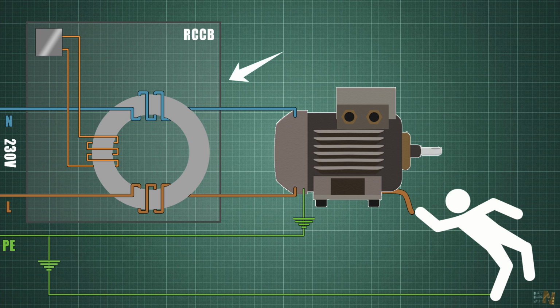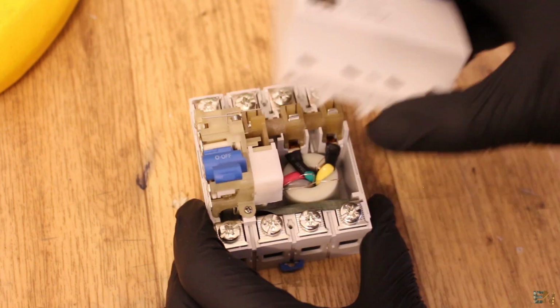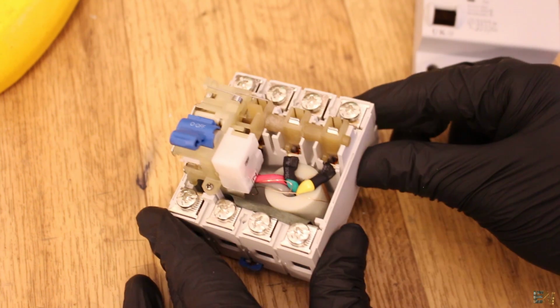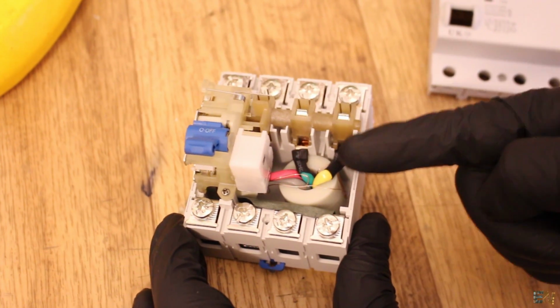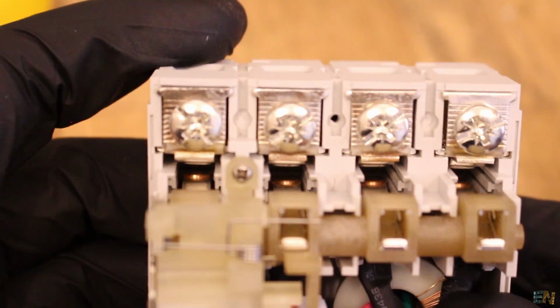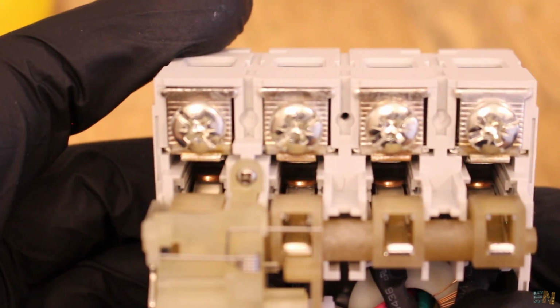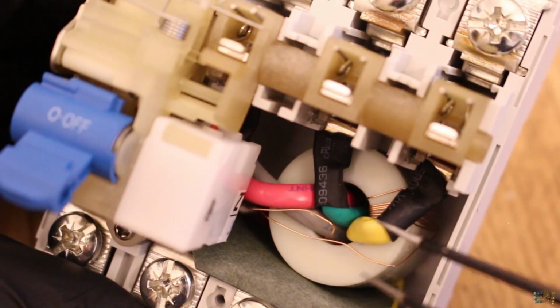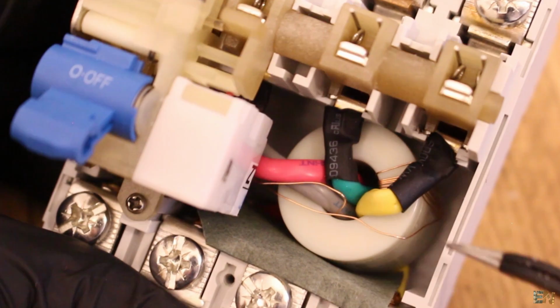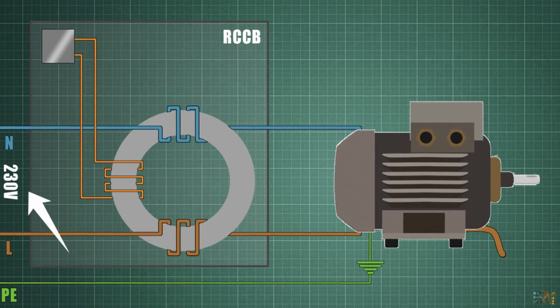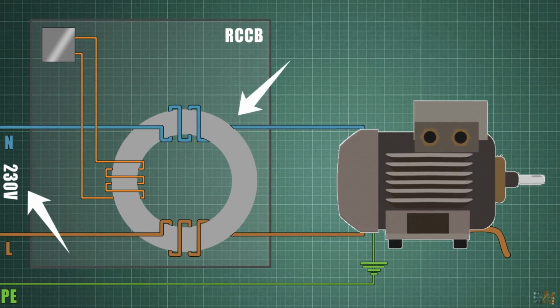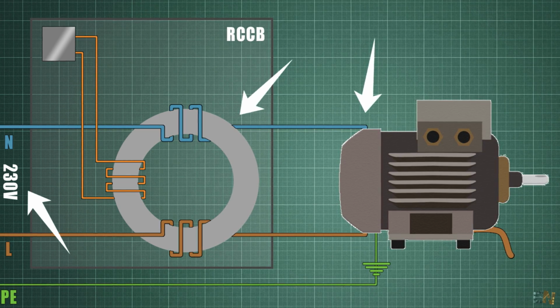If we open this RCCB, which in this case is for 3 live wires, we will see some kind of transformer and some winding around it. And then we have some connectors for each of the live wires and neutral. But the magic is done by the small transformer, and this is how. So here we have the main input, the RCCB transformer and the load that we have connected.